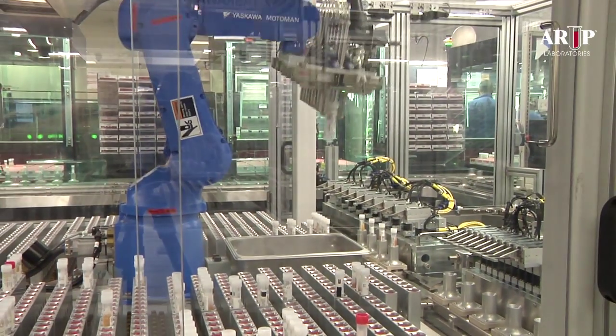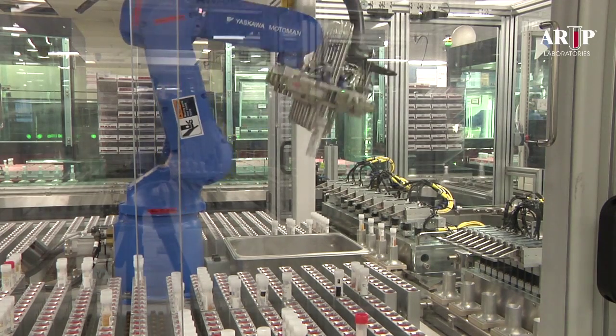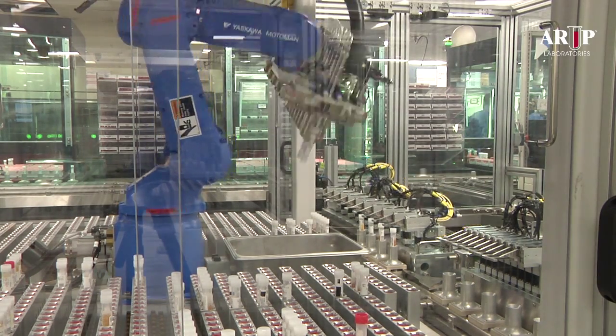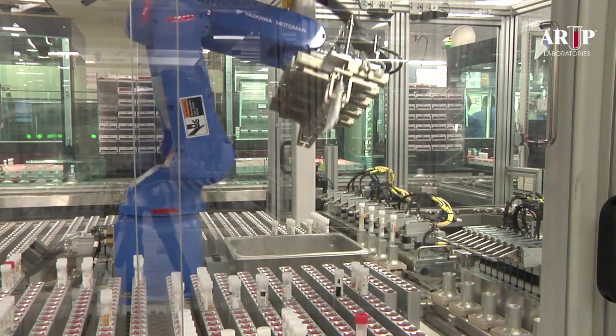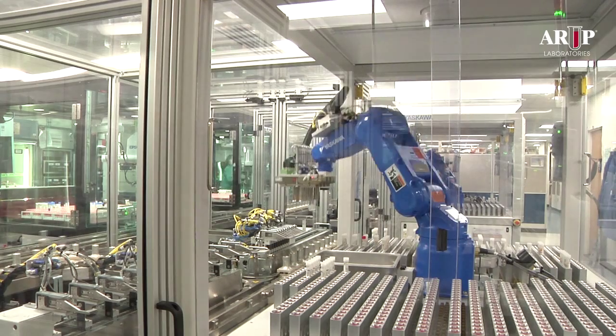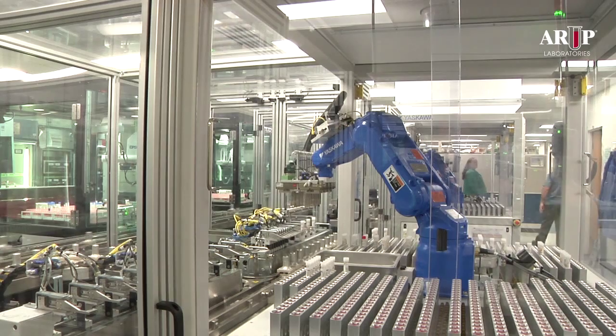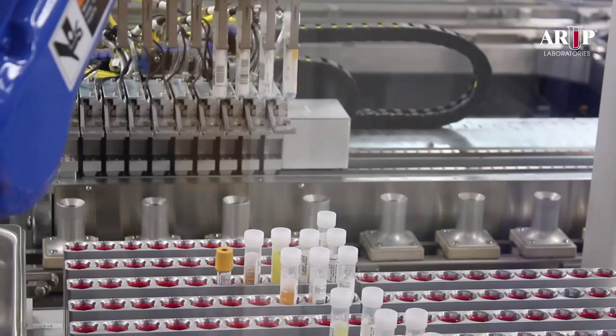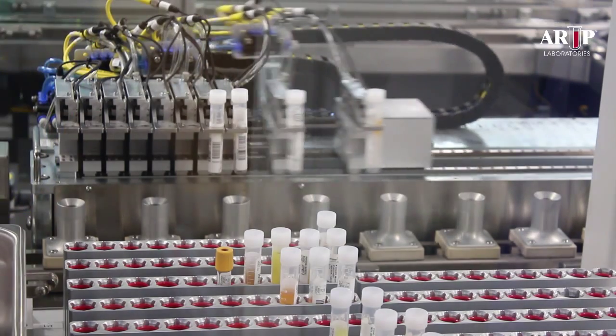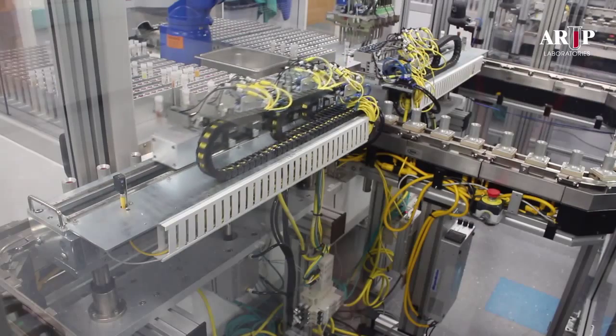At the end of the 25 minutes, the tubes are picked up by the robot, which mixes the thawed contents a total of 8 times with a 270-degree motion. When the mixing cycle has been completed, the robot transfers the tubes back to a third robotic system, similar to the one that unloaded the tubes from the pucks. This system spreads the tubes out to the 3½-inch intervals at which empty pucks are waiting, and lowers the tubes into the pucks.